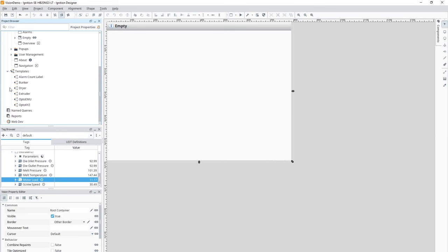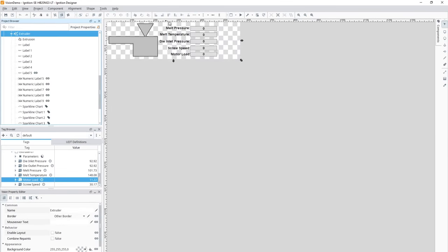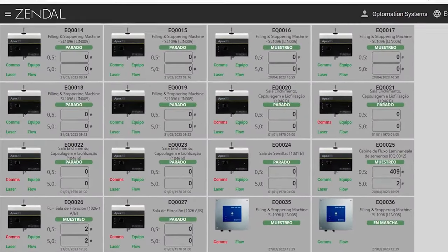Templates are a simple but very powerful feature in Ignition that you can use with Vision windows. The power comes from the ability to modify only the template in one location while affecting all of the instances used throughout the project. HMI and SCADA systems typically have a lot of repetition in their screens — you might use a group of the same components over and over again. You can make a single template and use instances of it repeatedly, effectively leveraging object-oriented design.